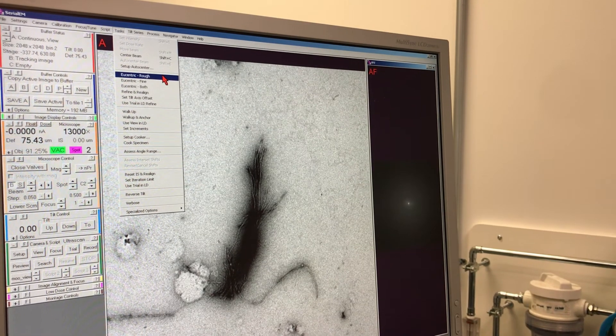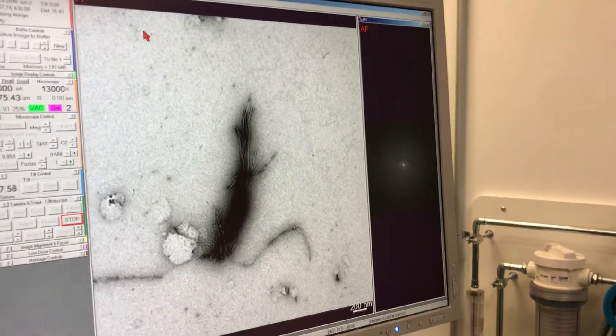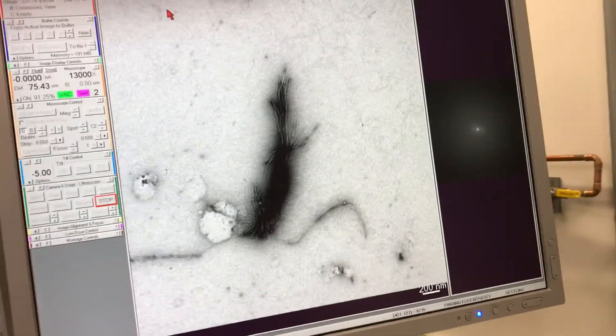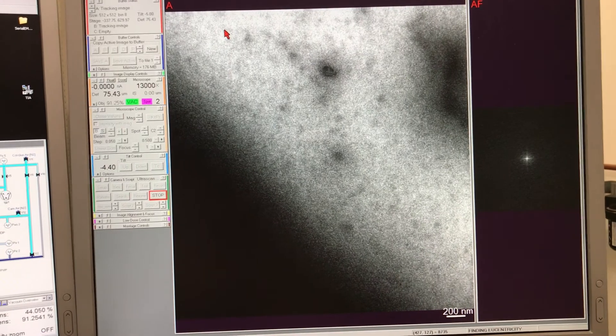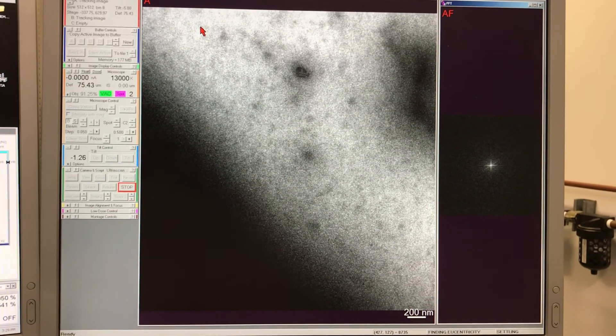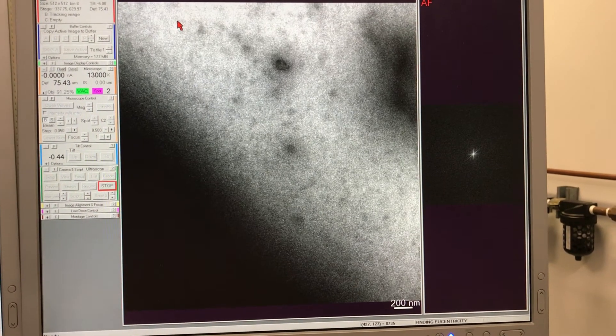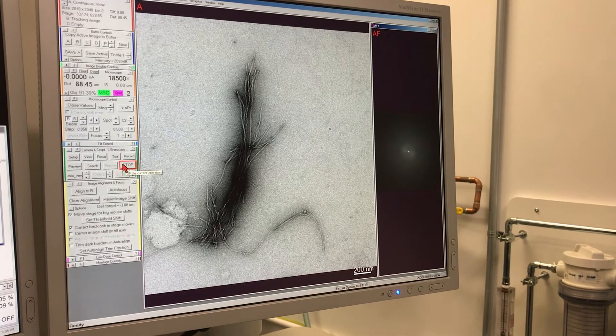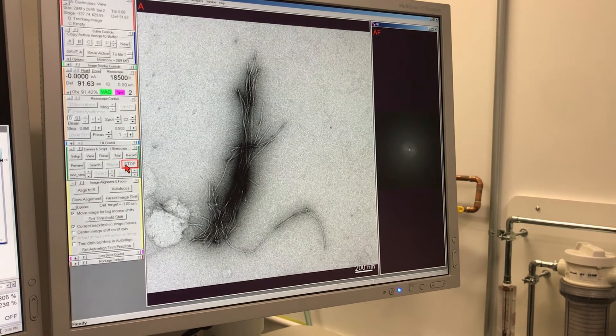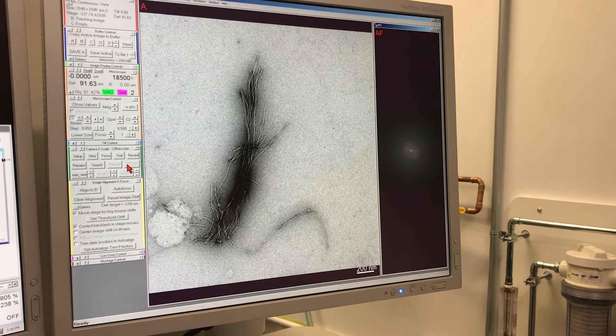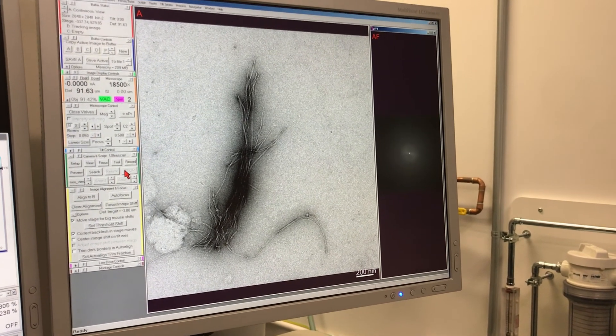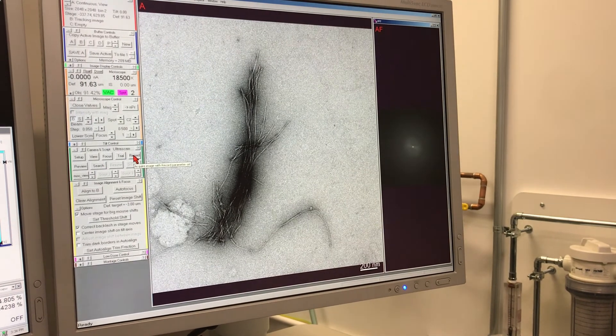As you can see, the wobbler in the goniometer will try to adjust the height by tilting the stage to plus 15 degrees and minus 15 degrees from the original position until the image that we see doesn't move for whatever tilt angle that we are using. It's also possible to set the Z height or eucentric height using the control panel for the microscope. In our case we're using software to do this, but it can also be done manually.